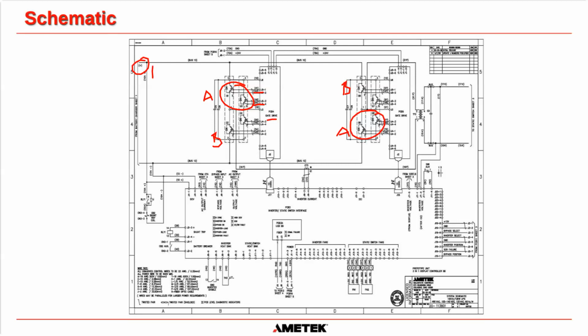Here is our positive, so we've got our positive there, and we've got our negative down here. And if we follow it through, if we turn A on, power flows down through these IGBTs, down through both of them. Then there's a bus bar connected here that is connected to this wire. That wire goes out down here through this transformer. And then that gets to the negative by going down here through these two IGBTs that are connected in parallel, down to our negative circuit here. So it is a bit more complex to look at because the control board and everything else is there, but we are creating a PWM signal.